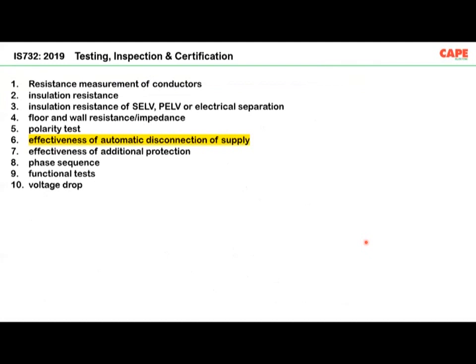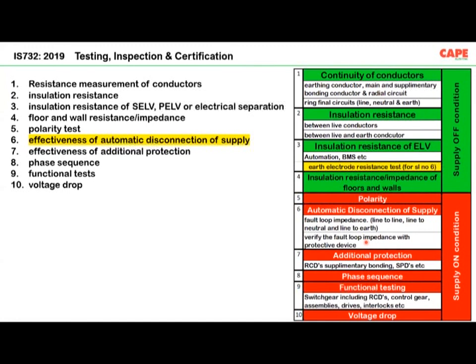IS 732-2019 recommends 10 different kinds of tests, and one of them, number 6, is effectiveness of automatic disconnection of supply. What it means is, for getting fire protection and shock protection, you are supposed to disconnect your supply, for which you must ensure that your device is able to disconnect within a certain time by making this particular test. So basically, modern electrical installation standards are asking for 10 different tests. Out of these 10, 4 are in supply off condition, and 6 tests are in supply on condition.